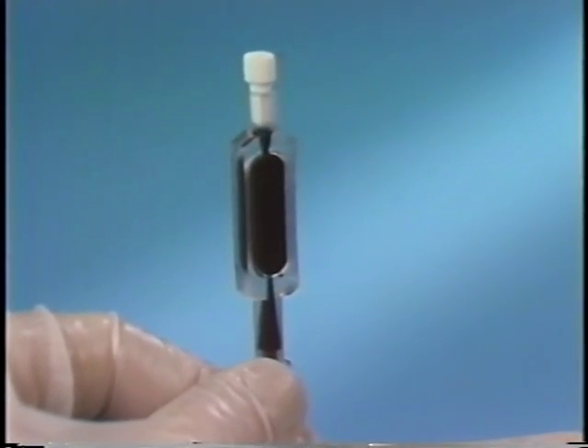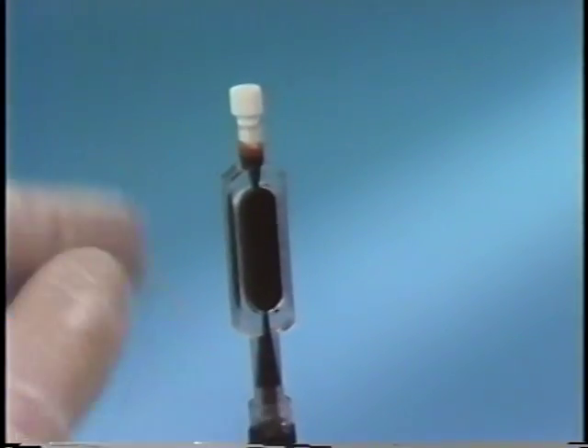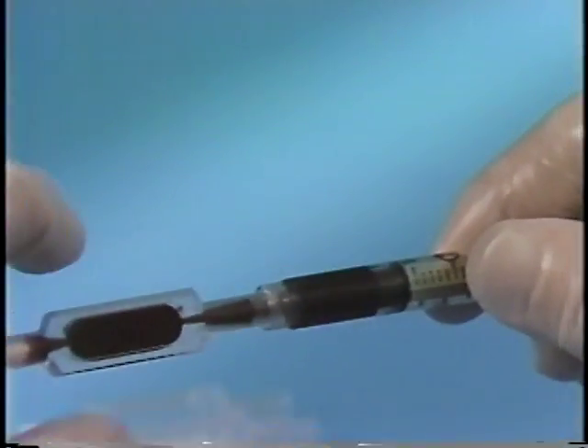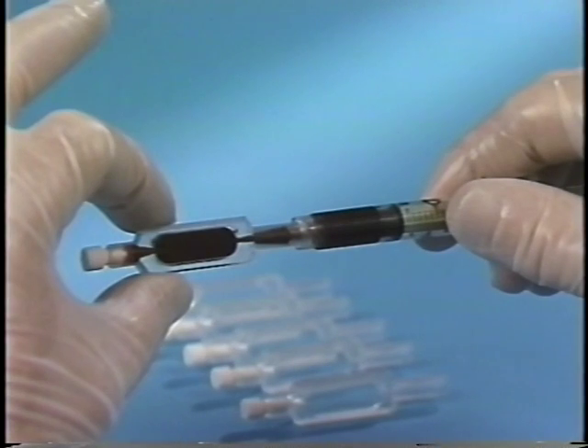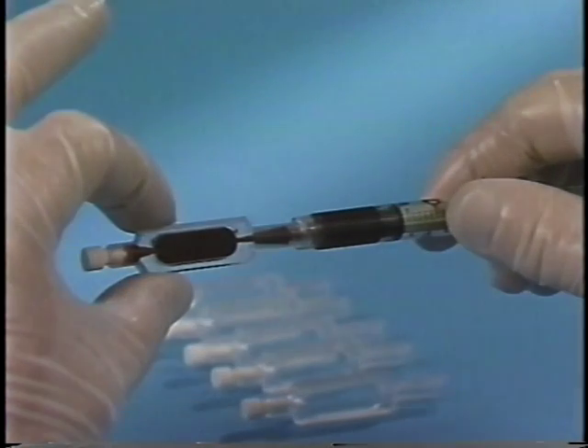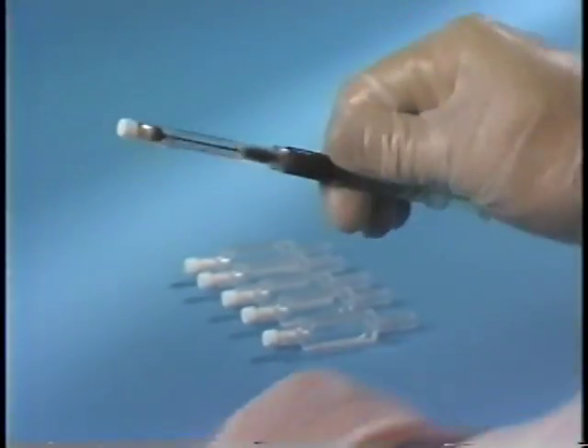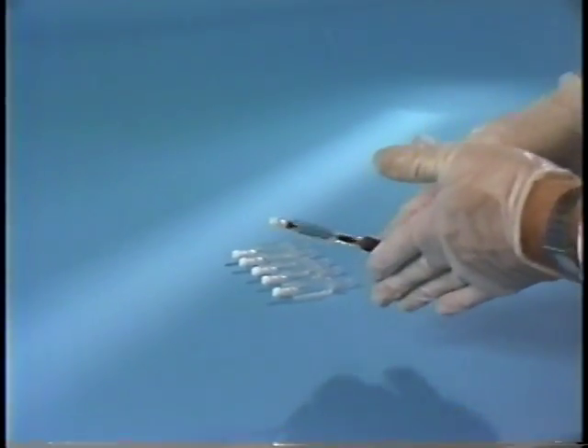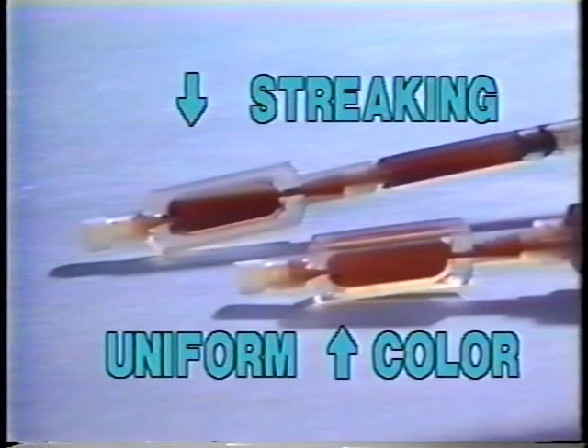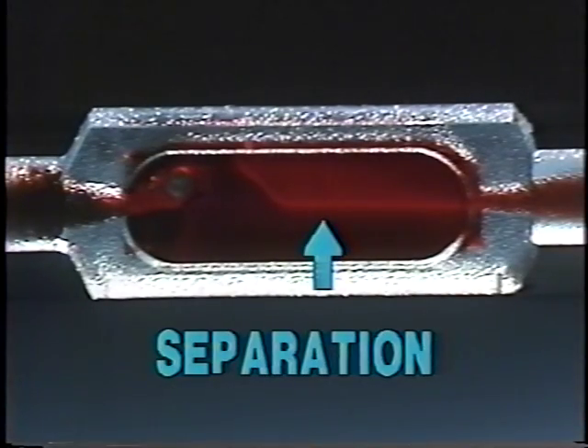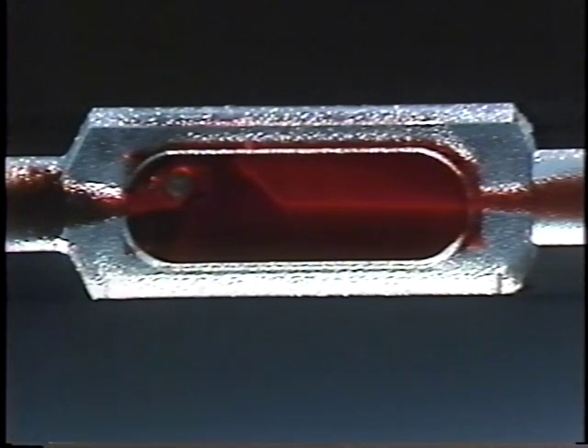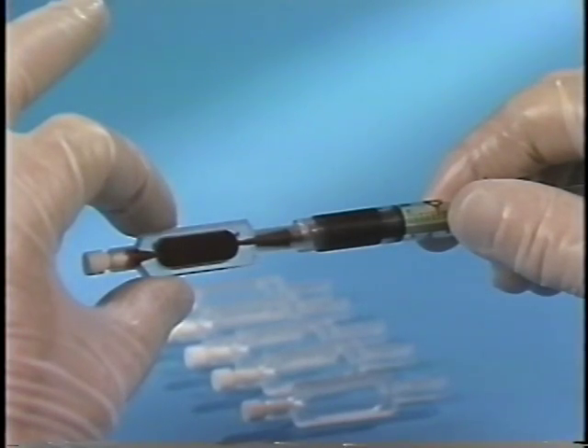Fill the cuvette until the blood permeates the lower part of the filter. Once pressure is felt, stop. Note that no contact is made with the cuvette windows. The sample should be rolled in the horizontal position to ensure a homogeneous sample and avoid settling. A well-mixed sample has uniform color without visible streaking, color disparities, or separation. The sample is now ready for analysis.